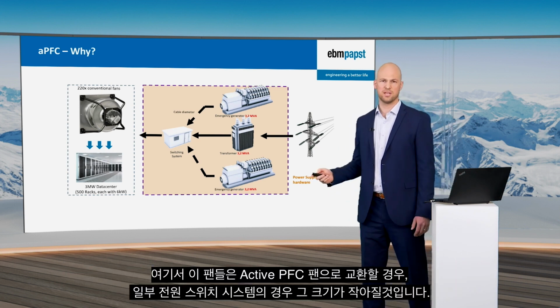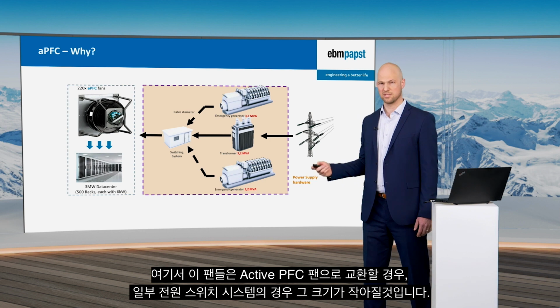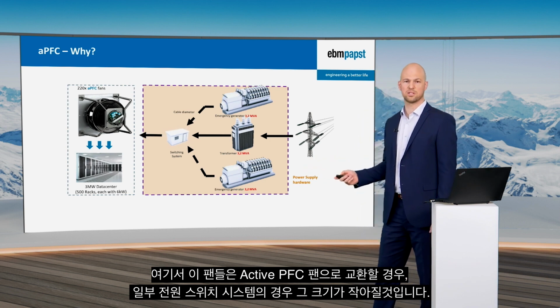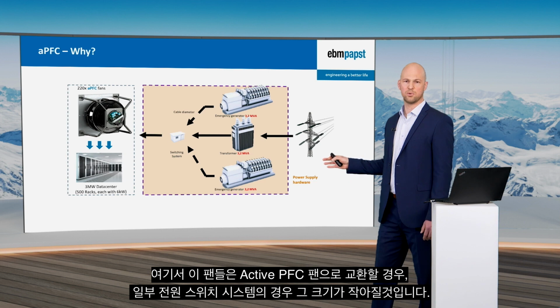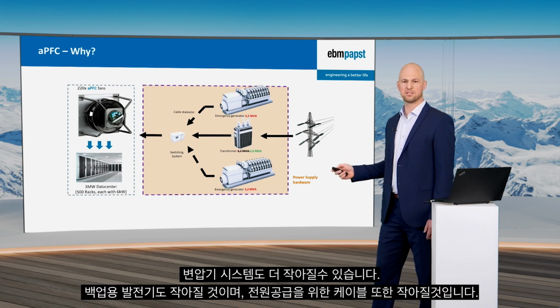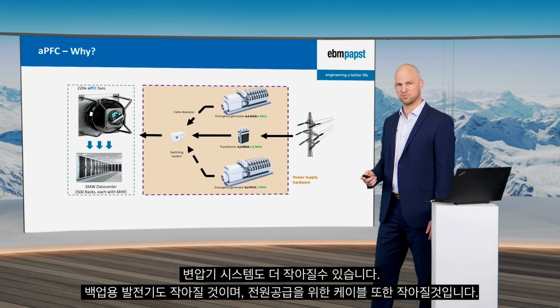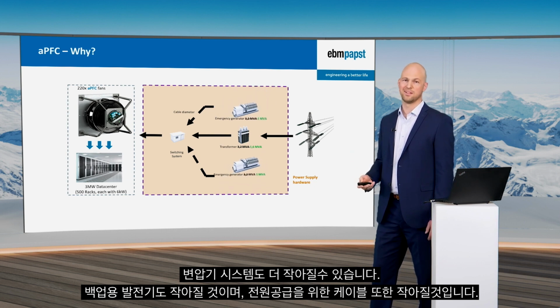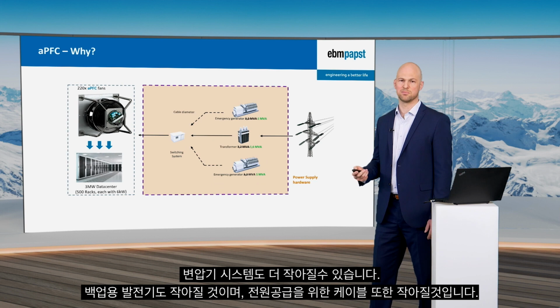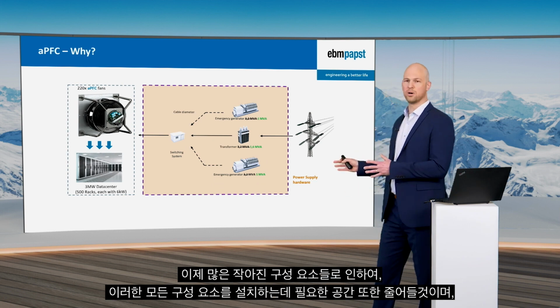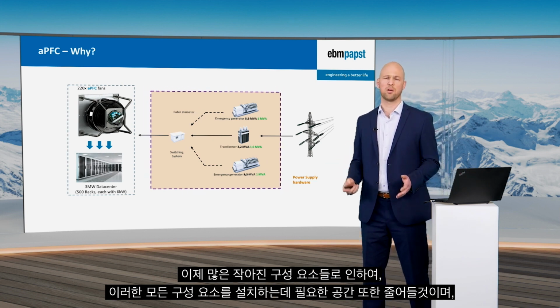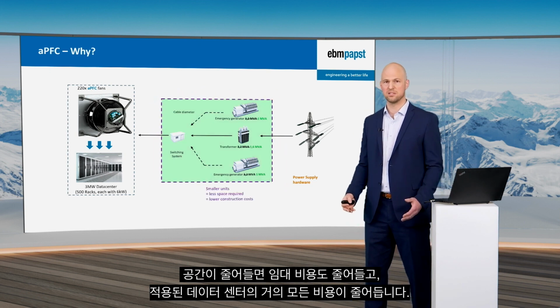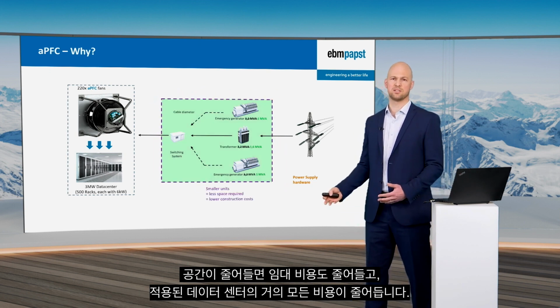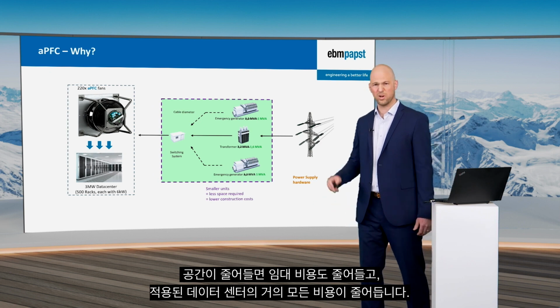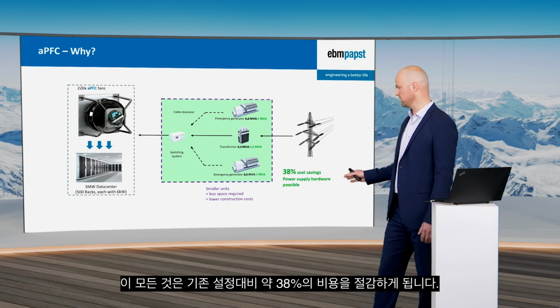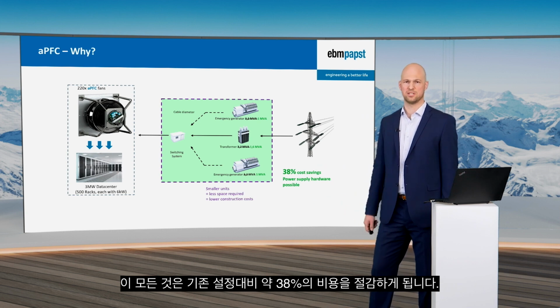When we exchange these fans for Active PFC fans, we can save on several components. For example, the switching system can be dimensioned smaller, the transformer supplying the installation can also be smaller, and the backup generators will be smaller. Also the cables will be smaller. Since we have a lot of small components now, we also need less space to deploy all of them, and less space means either less rental costs or more space for the data center to be deployed. With all of that, we can achieve savings of about 38% compared to the conventional setup.